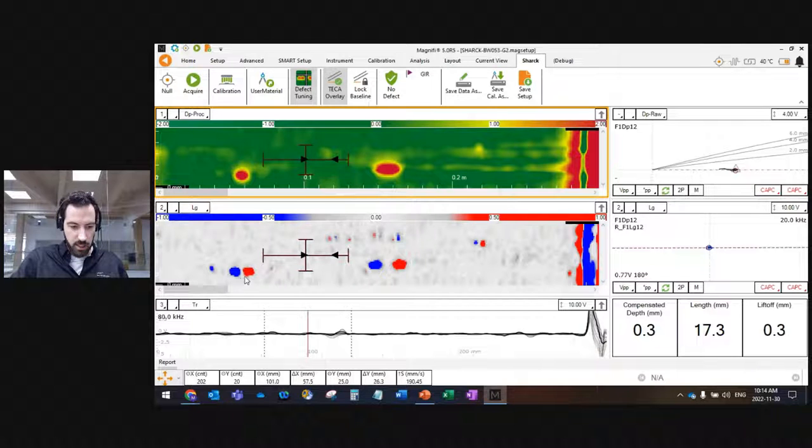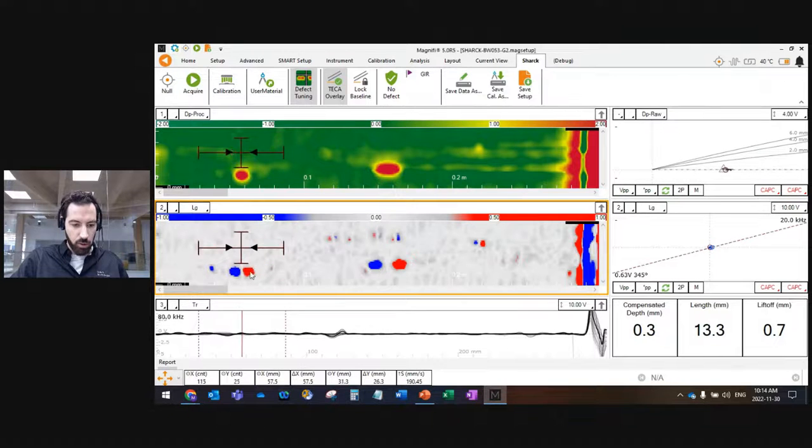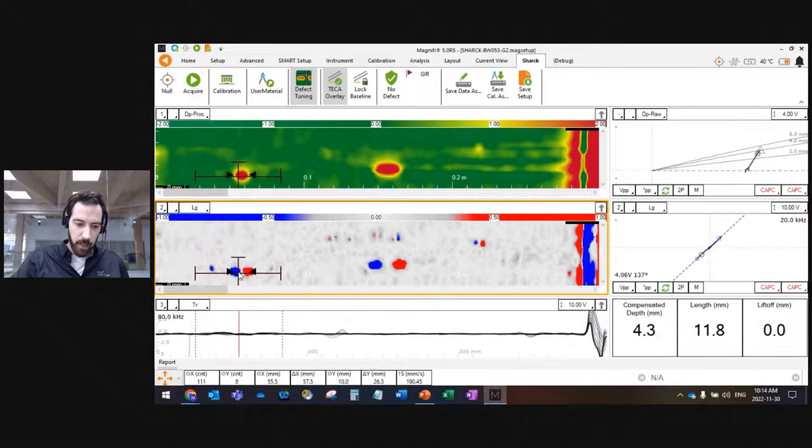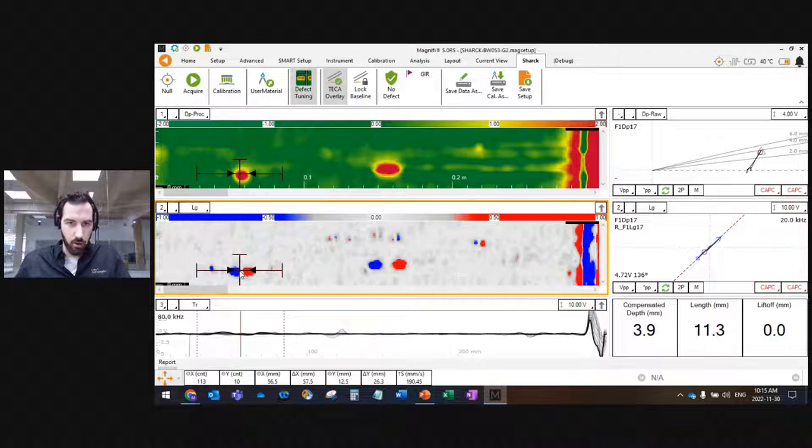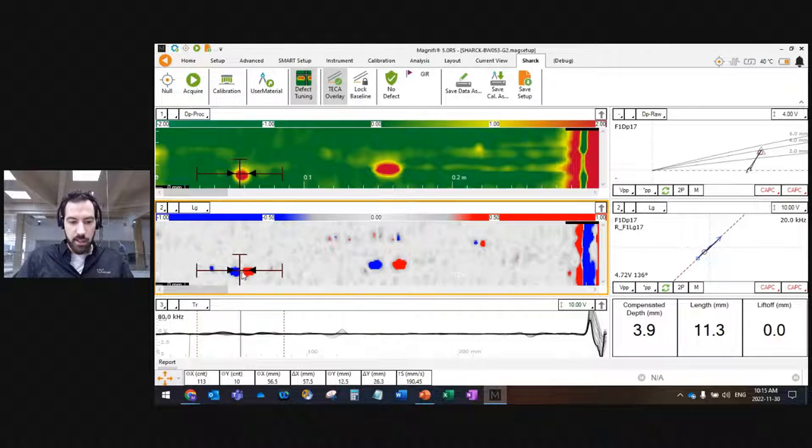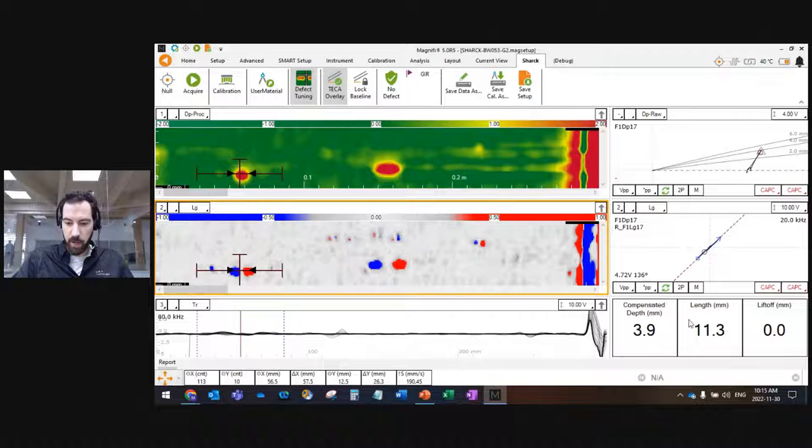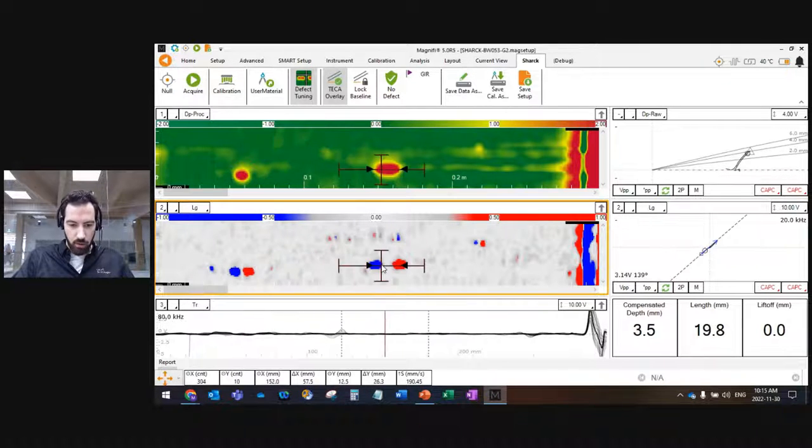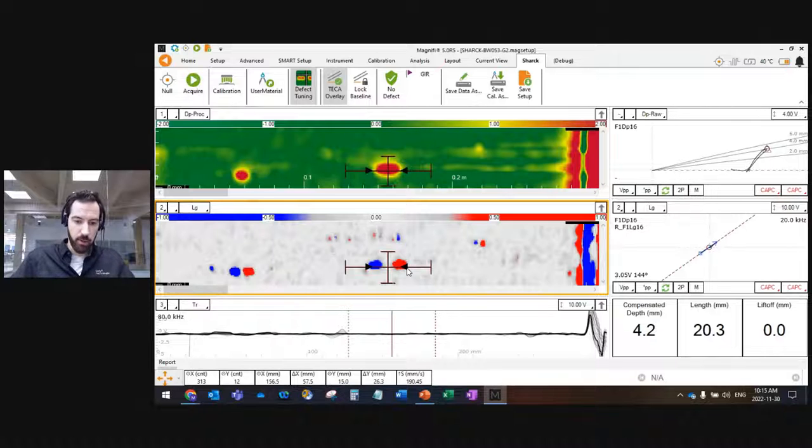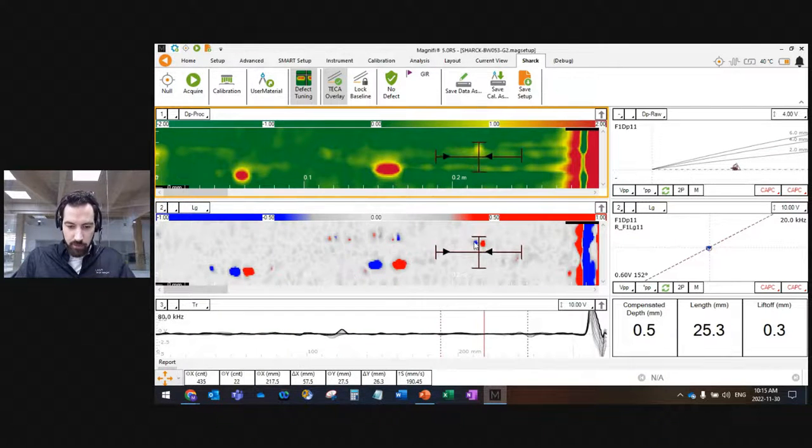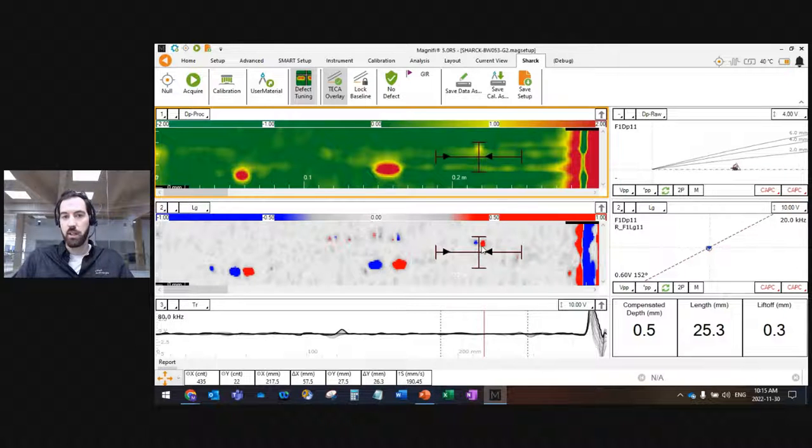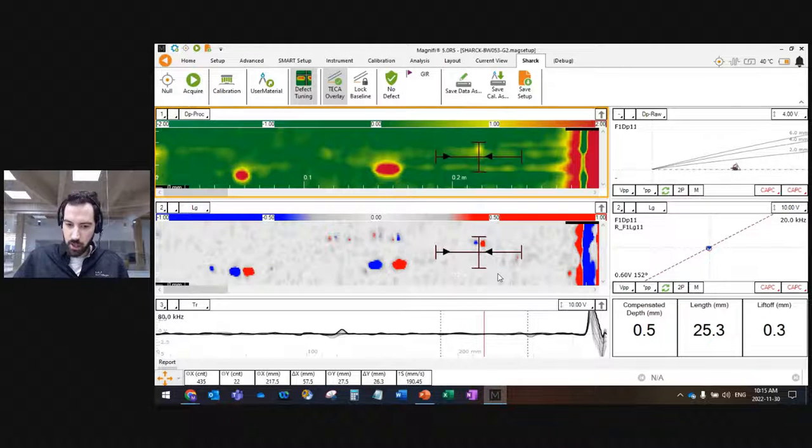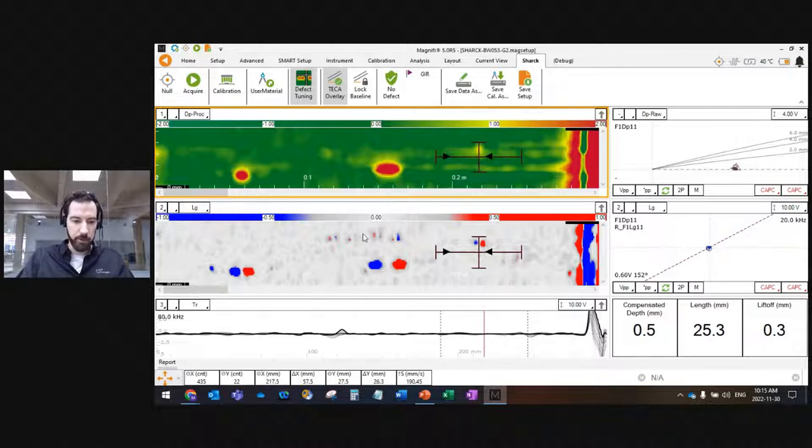The blue and the red dots are the beginning of my crack and the end of my crack. This is useful, first of all, to make sure that this is really a crack, really a surface breaking defect that we're inspecting. But this is also useful to measure the length of the flaw, because all you have to do is take the beginning and end and the software automatically calculates the length. Another one here, we have this blue-red combination telling us this is actually a real crack. And the third one we were not sure about, you also have this blue and red combination, so there is something there. Maybe it's not a deep crack, maybe that's why it shows as a shallow and pale signal, but there's definitely something there.